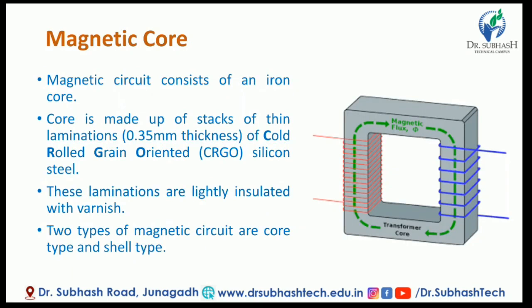The magnetic core — the magnetic circuit consists of an iron core. The iron core is made up of stacks of thin laminations. These are cold rolled grain oriented silicon steel laminations of 0.35mm thickness. The laminations are lightly insulated with varnish.